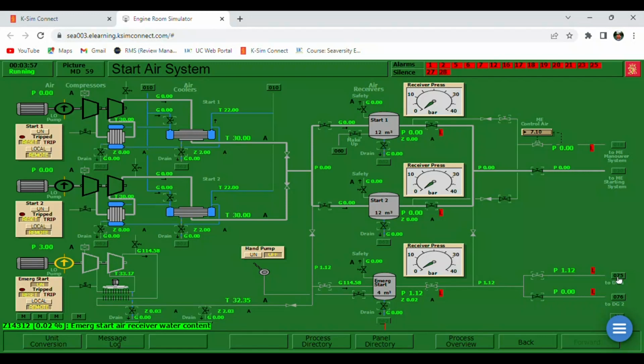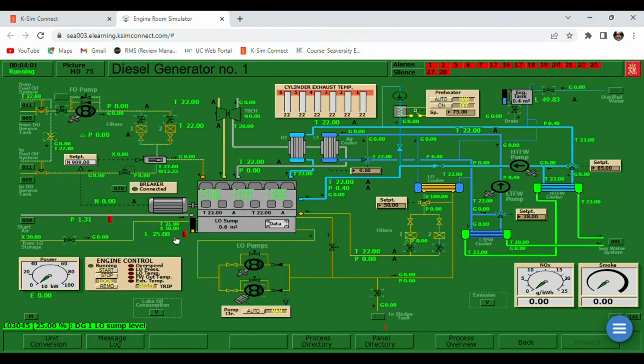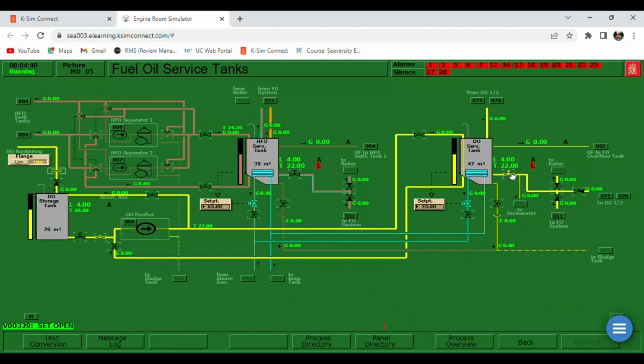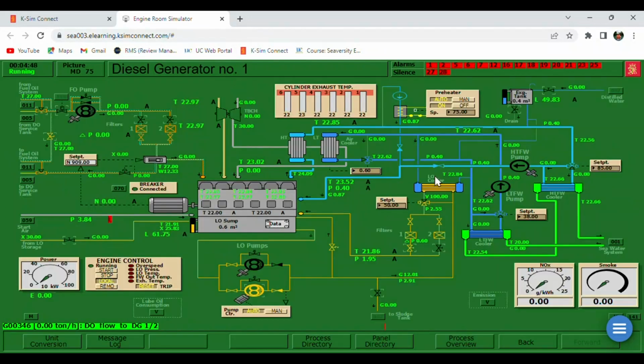now it's increasing. So let's go back to DG1, and as you can see, we have low level on the sump tank. We need to top it up. And we need to set up the lines of our lube oil system. Put this pump on automatic. You can also put the preheater to automatic. Once the level is normal, we can close this valve and continue here. We can use diesel going to our DG1, so we need to open these valves going to DG1 and 2. You can also open to the fuel oil system to the boiler. Okay, open this shuttle valve, also this valve.